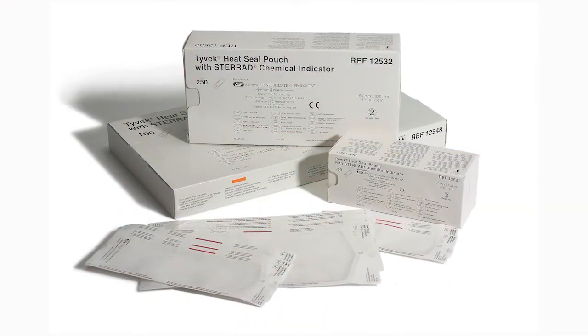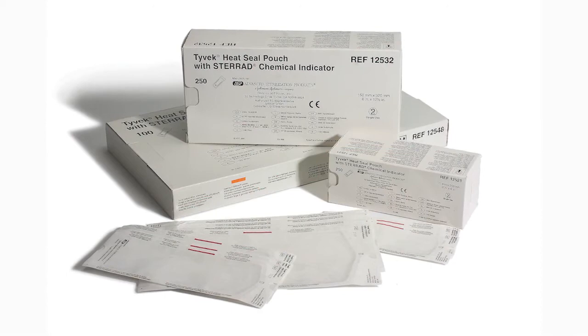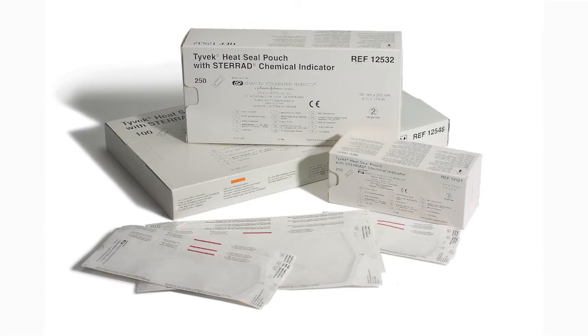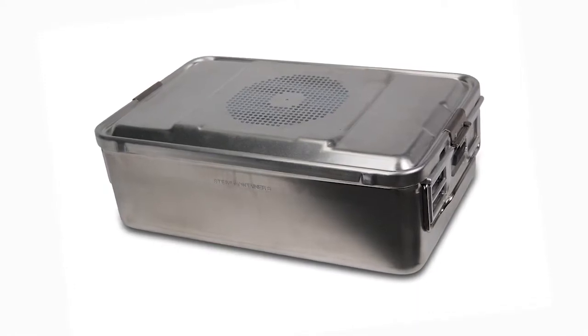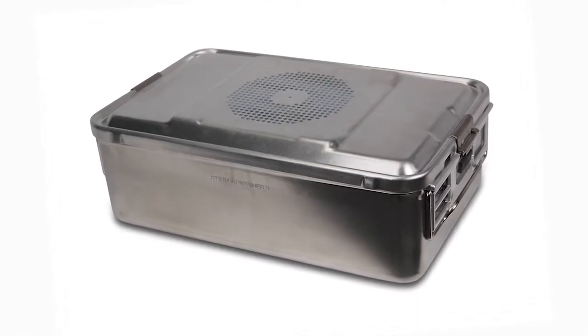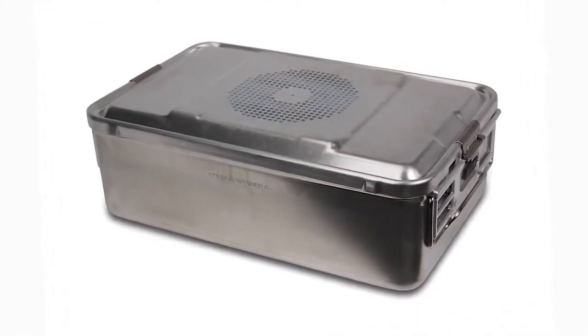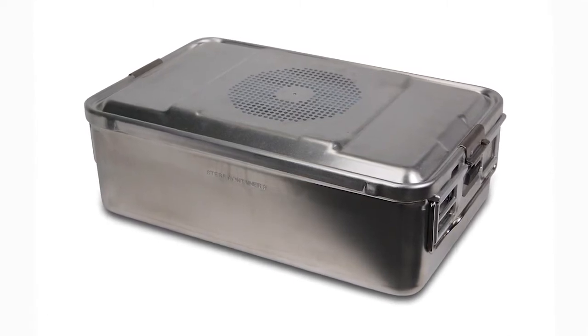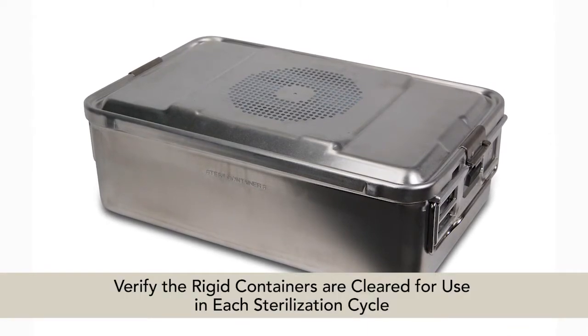Tyvek pouches and rolls with STERRAD chemical indicators are the only pouches and rolls available on the market that are validated by ASP. If you are using rigid containers cleared by the FDA for use in the STERRAD NX sterilizer, follow the instructions for use provided by the manufacturer. Verify that the rigid containers are cleared for use in each sterilization cycle.